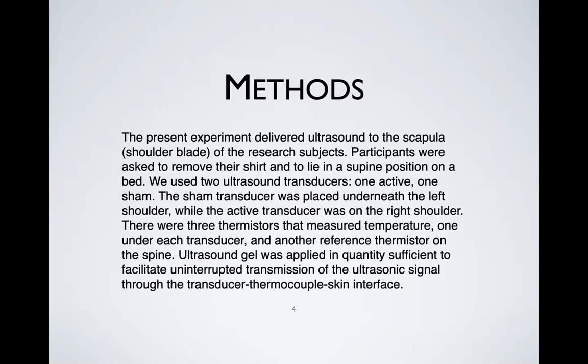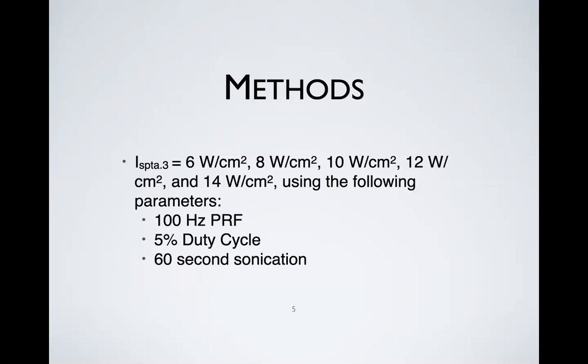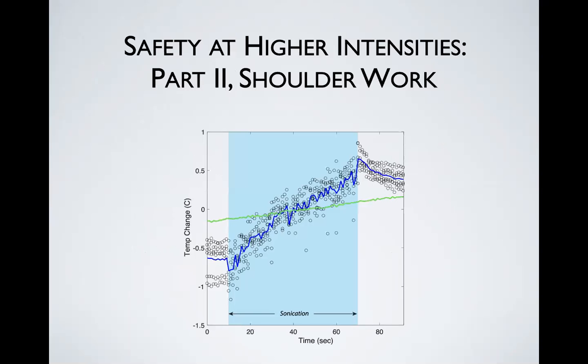We used sufficient ultrasound gel to allow for uninterrupted transmission of the ultrasonic signal through the interface. We had 5 different intensity levels, 6, 8, 10, 12, and 14 watts per centimeter squared, using the following parameters: 100 hertz pulse repetition frequency, 5% duty cycle, 60-second sonication. It's also worth noting that we use the BrainSonix system, which uses a 650 kilohertz fundamental frequency.